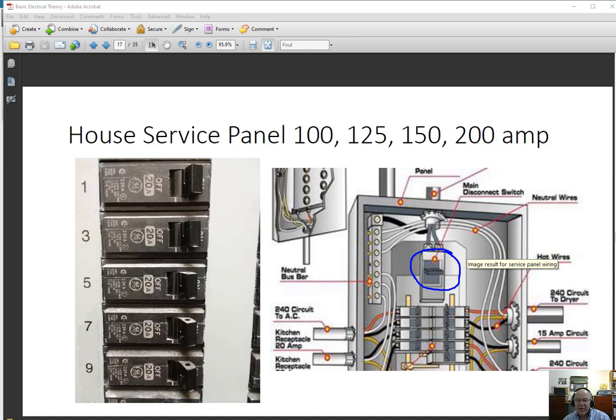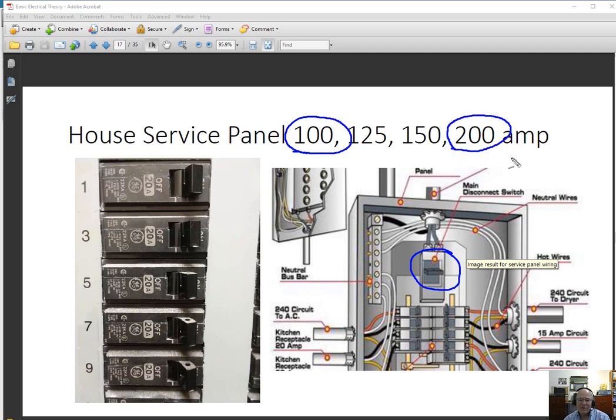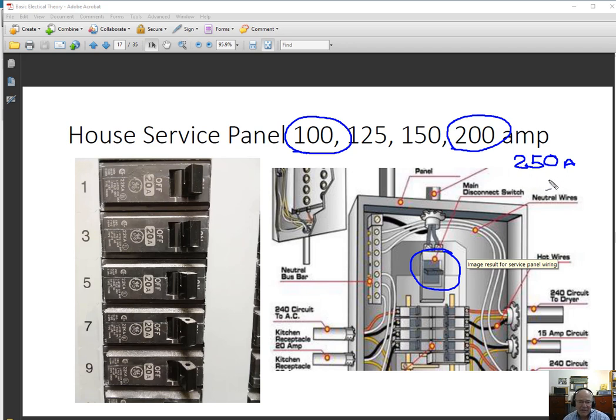That main breaker is carrying 240 volts. The amps it's carrying depends on the load requirements in your home. My house has fairly low electrical demand — even with an electric car, I have 100 amp service. It used to be fairly common to have 125 or 150. Now, almost every home being built has 200 amp service. Jake tells me he worked on a home that had 250 amp service. The reason why that number is so high is because we keep increasing the electrical load by adding more and more appliances. A 250 amp service probably means a very large, fairly expensive home — maybe with a three-car garage or a shop.